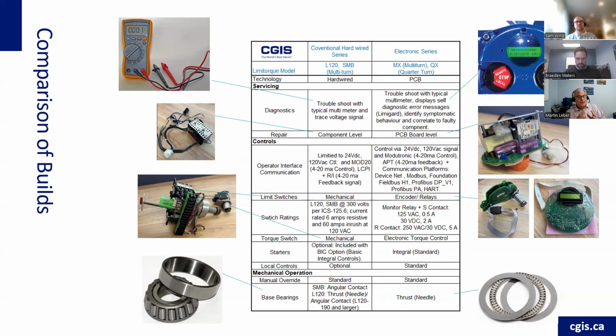So what the service guys typically do is ask, well, what's it doing? What's it not doing? What's the symptom of the actuator? Then they'll say, if this is happening and that is happening and you're getting this readout, then we know it's this. So fault detection, yes, the Limigard software is excellent, and any manufacturer with that will tell you it's great. And it is great. But in reality, you also need the experience of understanding the symptom the actuator is experiencing. And then replacing the component is at a board level.